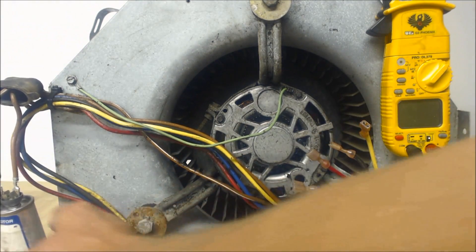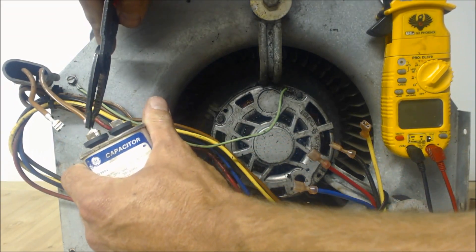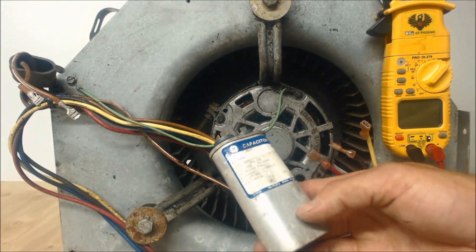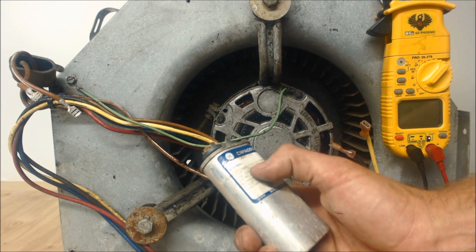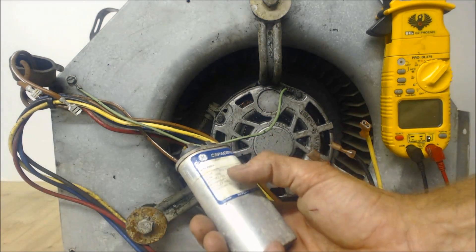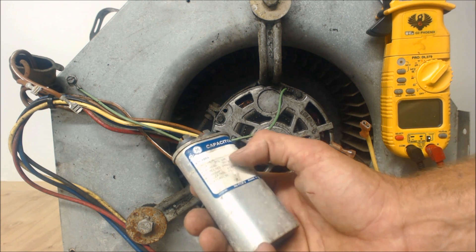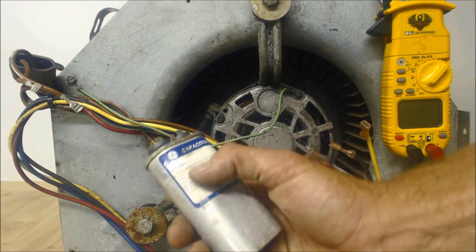With the power off, go ahead and disconnect the capacitor. You can pull those terminals off in any way — just be careful not to break the spade terminals. This particular capacitor is a 15 UF, which means 15 microfarads, and it's 370 VAC. If this capacitor was bad, you would want to replace it with the exact same, or a 370/440, or a 440 cap — any of those would work since this is a 370.